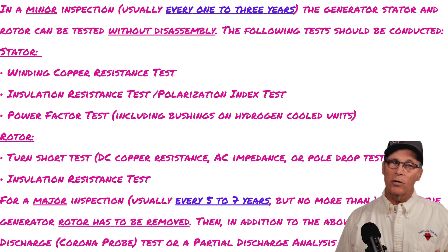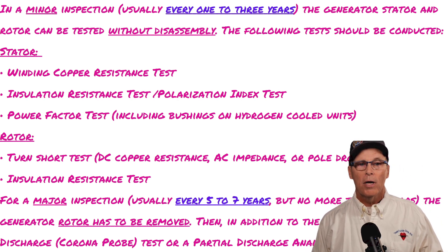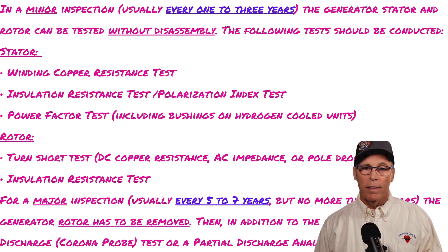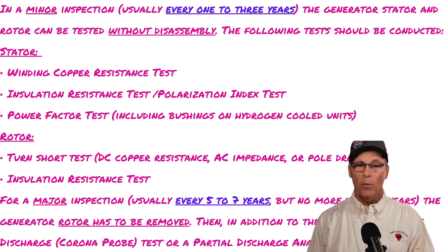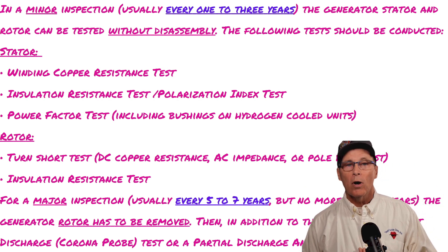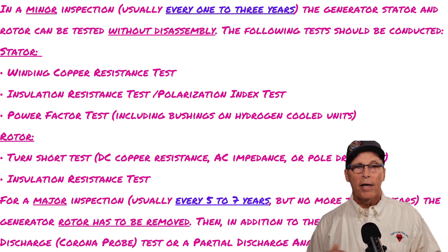Every five to seven years — no more than ten years — you're looking at a major inspection. You have to pull the rotor, or field, out of the stator. In addition to all the minor inspection tests, you perform a slot discharge corona probe test or partial discharge analysis. This framework came from one of the largest insurance company engineering groups, which has a workbook for power generation recommending these steps for keeping generators clean and healthy.